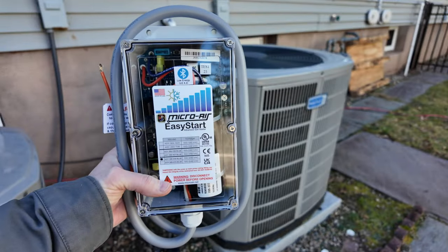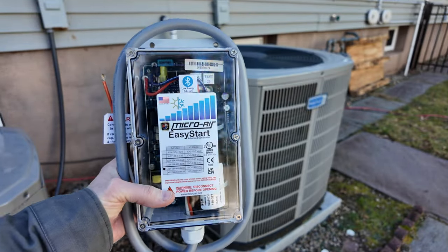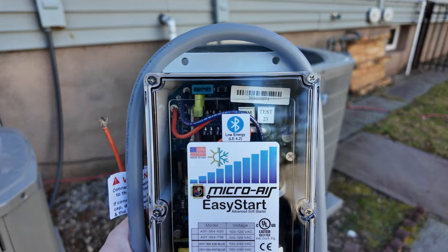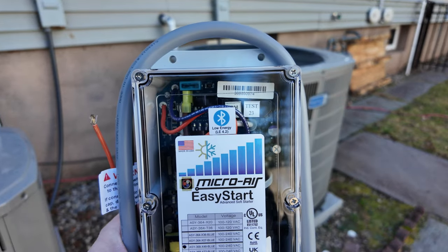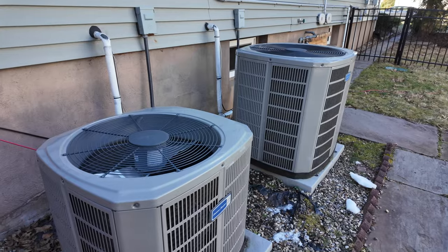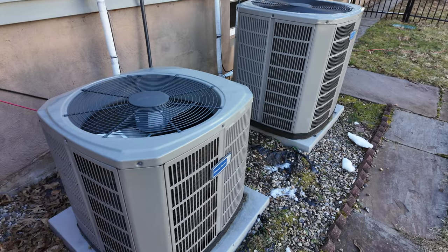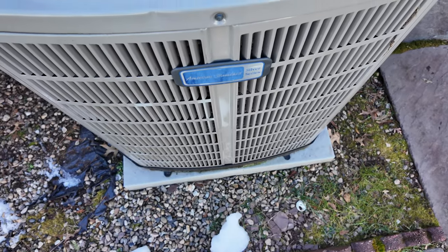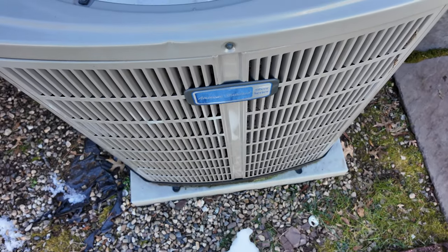So in order to do that, I installed a soft start on the larger 3-ton unit, just because although it would work, it would really make the lights dim. Adding the soft start makes it very, very easy for it to start up now. There's no issues at all with the Ultra using it.